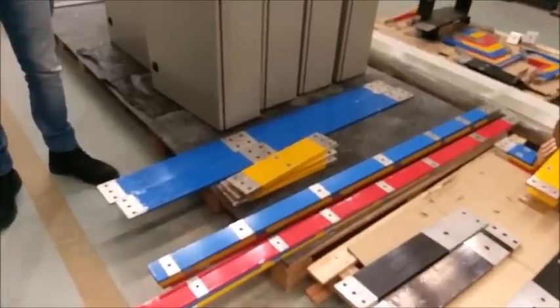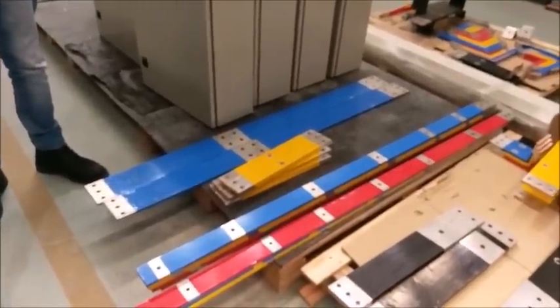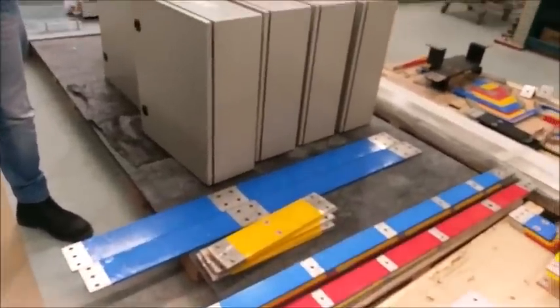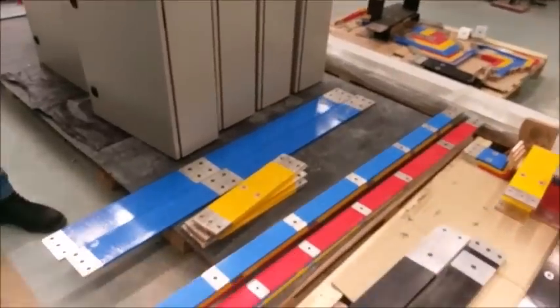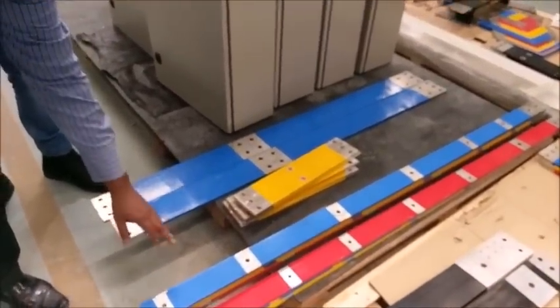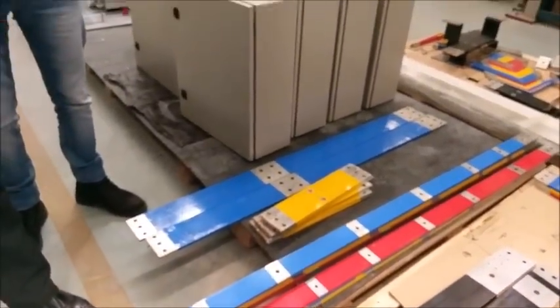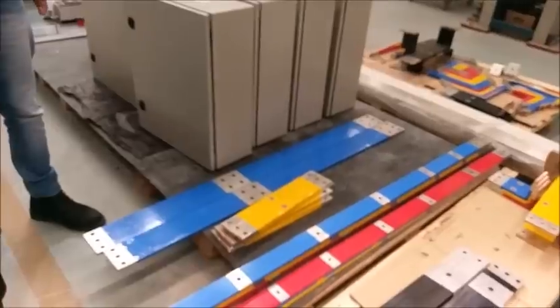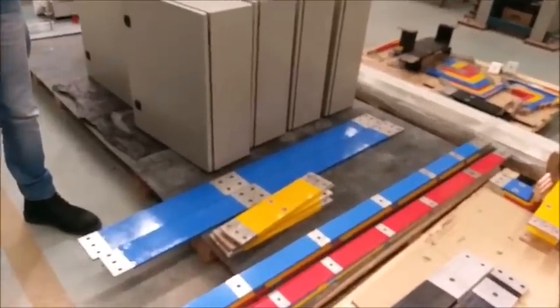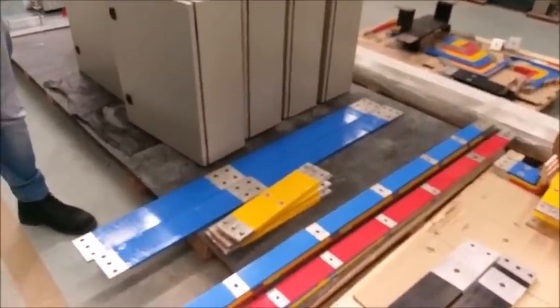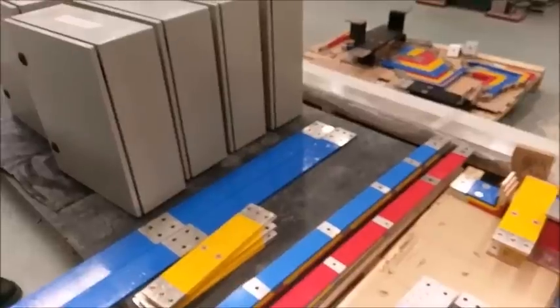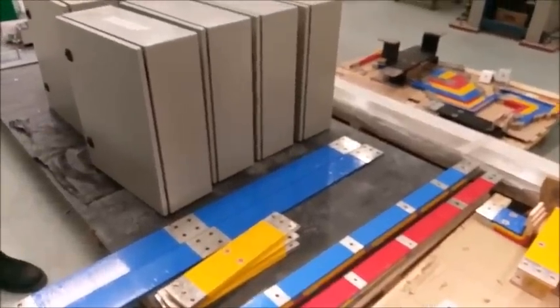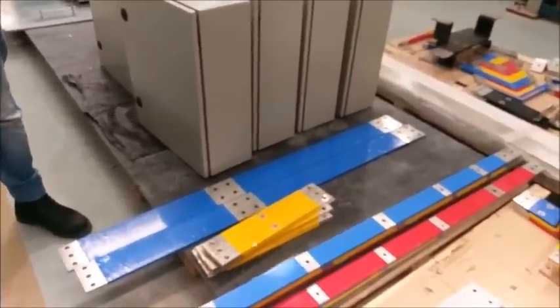So this will vary. This is the main horizontal bus bar, and this will be vertical droppers. All the bus bar sizes are as per type tested design, according to IEC 61439. You are following IEC. Yes.